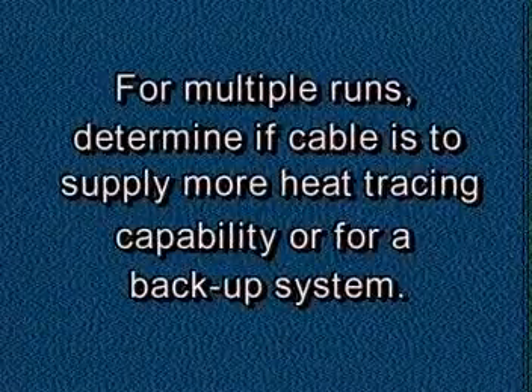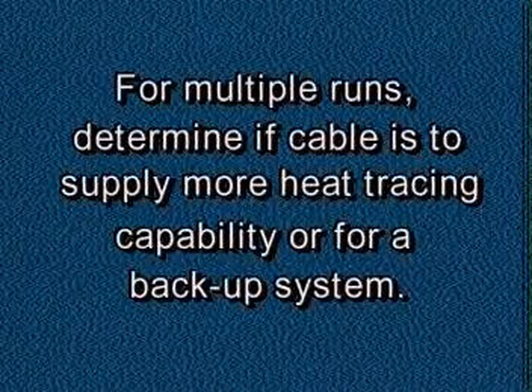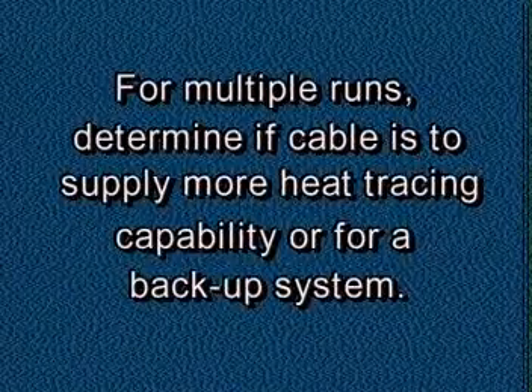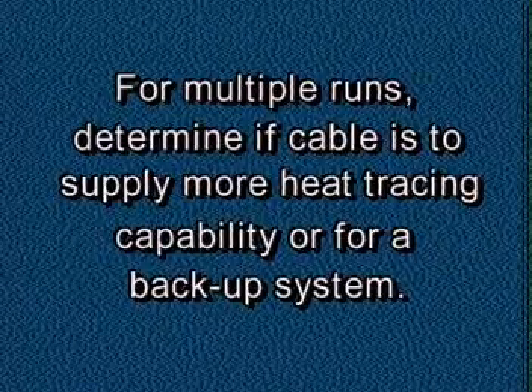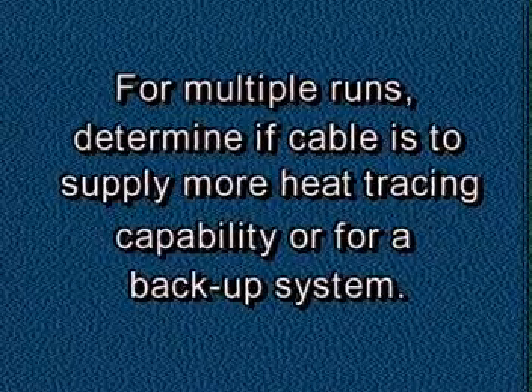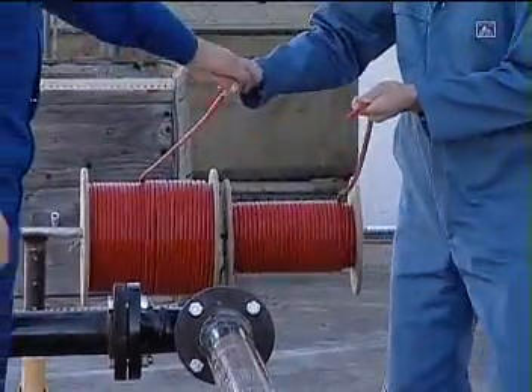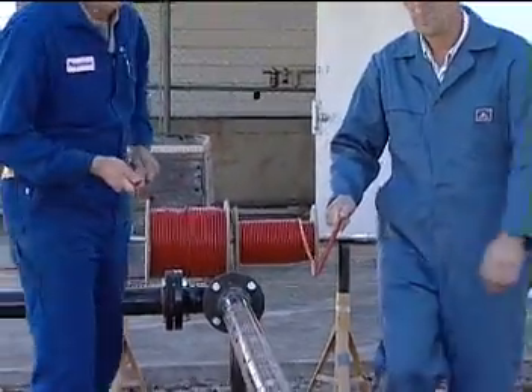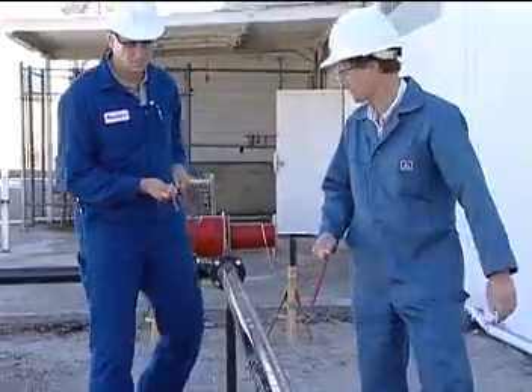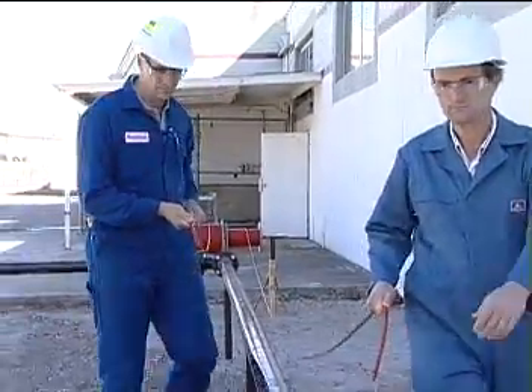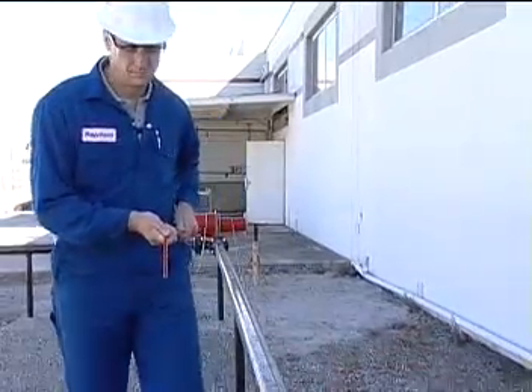Some installations require more than 1 run of heating cable. First, determine whether the additional cable is to supply more heat tracing capability or if it's for a backup system, because each system has a different installation procedure. When installing additional cable for more heat tracing capability, rather than pull cable from 1 reel as we previously saw, you can pull from 2 reels simultaneously to make the job easier.